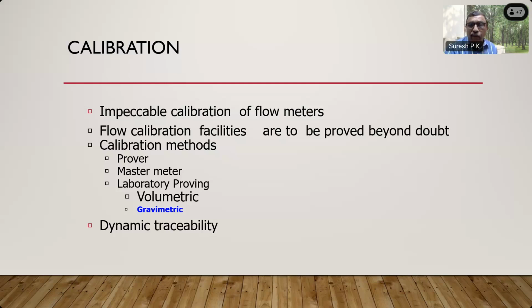Maybe due to human error, maybe due to instrument error, maybe due to a combination of instrument and human error, maybe the system under which it is being operated. Something which is to be operated at 20 degrees centigrade, you are not maintaining 20 degrees, you are maintaining 25 degrees, then there can be an error. So these kinds of things will come out during the dynamic traceability. Dynamic traceability ensures that your system is at par with international level systems. So it is mandatory, primarily for your confidence, not only for the law. So dynamic traceability is that. So you have static traceability as well as dynamic traceability for the calibration systems.